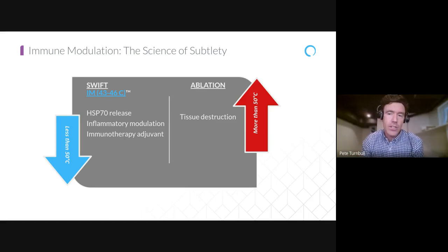And what they realized is that when they kept the actual temperature range below 50 degrees, so at a non-ablative level where you aren't destroying tissue, and you keep it into what we call the hyperthermic range, which is between 43 to 46 degrees C, just enough to very quickly elevate tissue temperature, but then allow it to drop down between your doses of energy. What you were getting is this release of what's called heat shock protein 70. And that's the key to upregulating your Langerhans cell activity. So it's like sending out a massive alarm signal to your body saying, we have a problem.